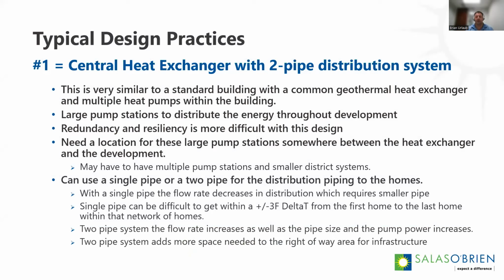So that's where we have a supply and a return throughout the district in every home or building that's connected to that district. Generally, if you think about in the past, when you would do a one-off building, let's say it's a school, you'd go out into the ball field, you put a common ground loop in, you'd pipe all that into the building, and then you distribute that through all the unitary heat pumps throughout the building. Well, this would be no different, other than you've got a common loop field somewhere in the vicinity of the community. You're going to pipe that supply and return throughout the community, and each home would then have its own unitary heat pump.